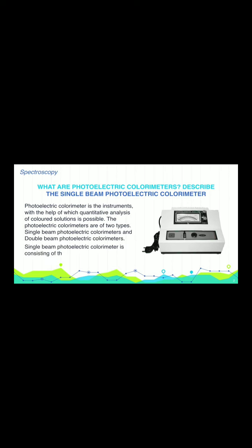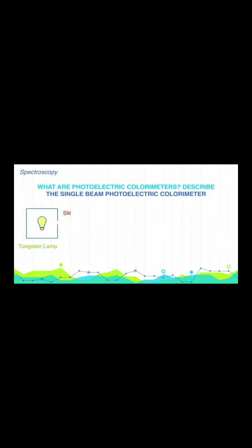A single beam photoelectric colorimeter consists of the following components. First, a tungsten lamp. A normal incandescent lamp with a tungsten filament is used. Second, a collimating convex lens. It collects the radiation from the source, and the transmitted radiation travels parallel to the principal axis because the source is kept exactly at the focus of the lens. Then there is a diaphragm. The function of the diaphragm is to set 100% transmittance.